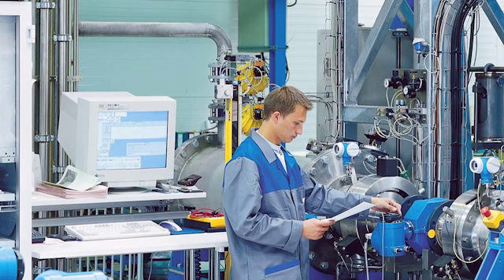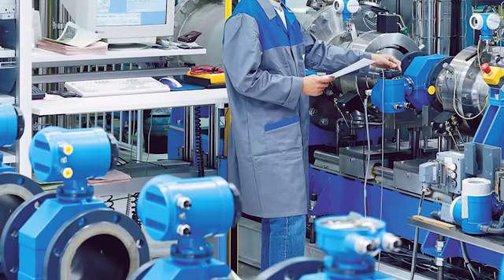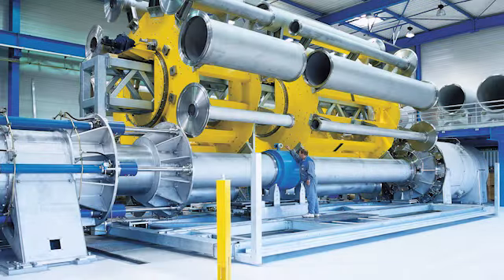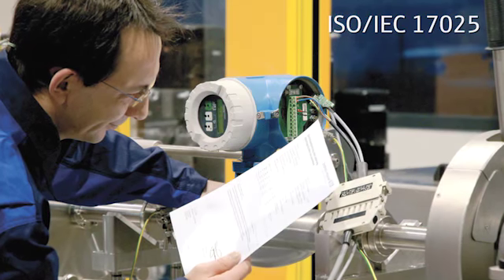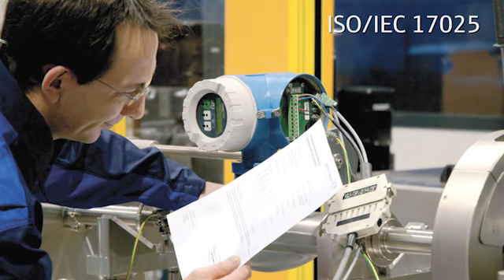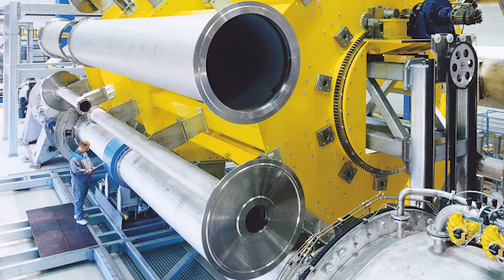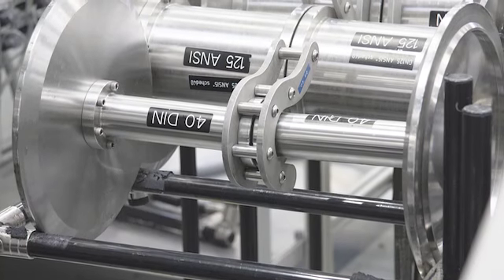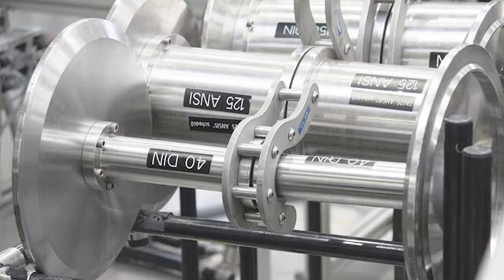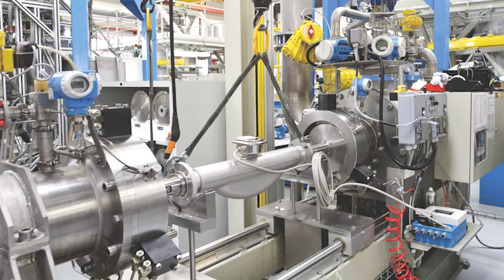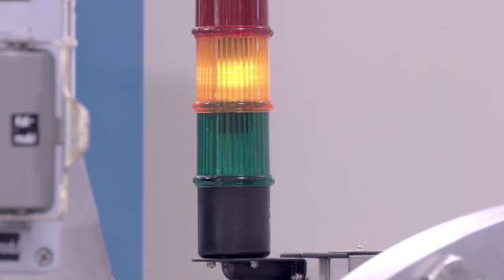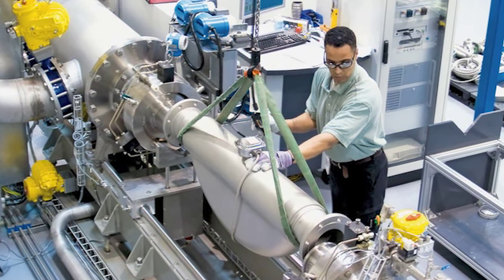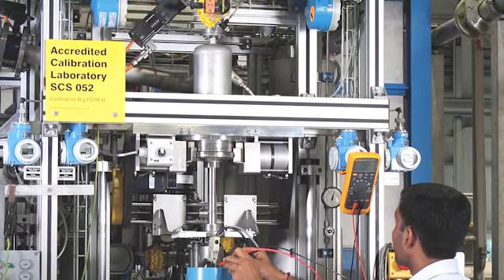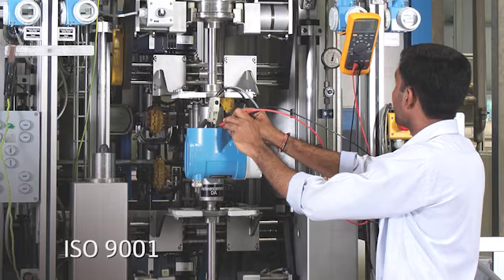Year after year, Endress and Hauser has been calibrating hundreds of thousands of measurement devices. Therefore, every one of our flow calibration rigs has been accredited by official agencies according to ISO IEC 17025. The fact that this is unique worldwide leads to the high degree of confidence in our metrology. During an accreditation process, various criteria are evaluated according to the most stringent quality standards, such as the traceability of test equipment, training of operating personnel, technical infrastructure, and quality management in accordance with ISO 9001.